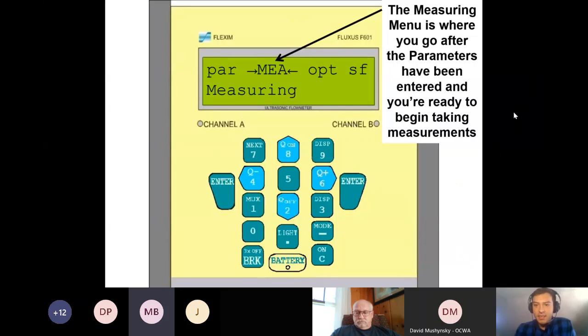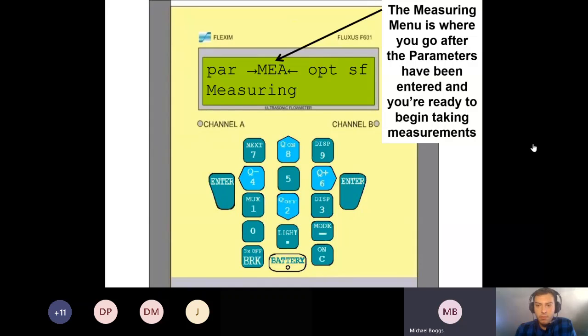Yes. Okay, you mentioned something about a stainless steel spool piece. Is that something we can order from you? Definitely, we can get you a stainless steel spool piece if you're having issues with a rusty or built up pipe. Are the transducers permanently mounted in them? Is that how that works? We could do a permanent mounting, but it's still the same setup. We would just be doing the spool piece, so you get a clean one. We read really well on stainless steel. With the solid coupling pads, it is a permanent installation, so you shouldn't have to touch it anyway.